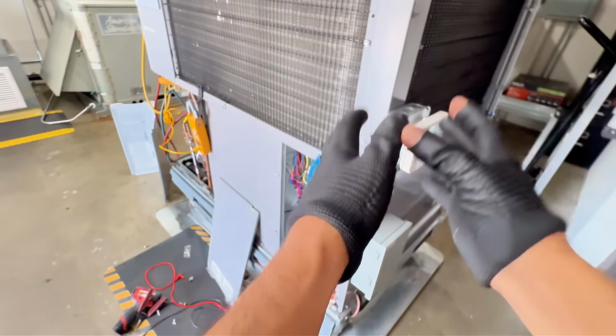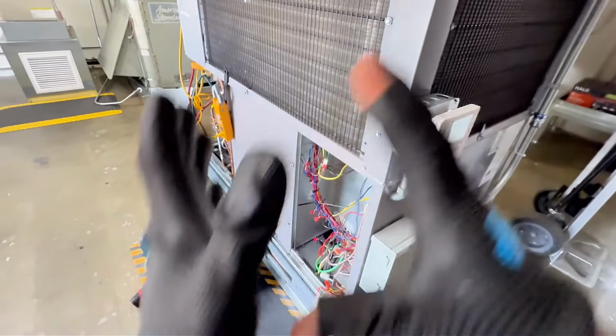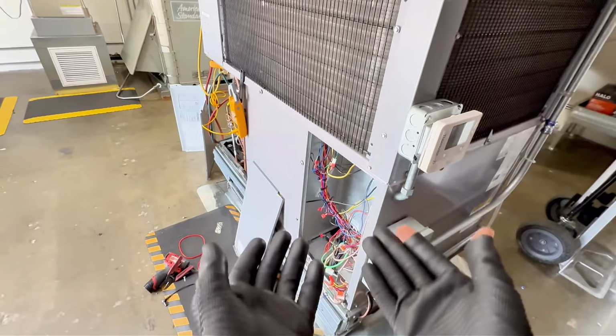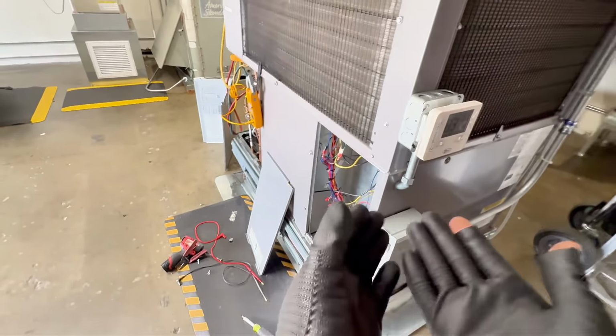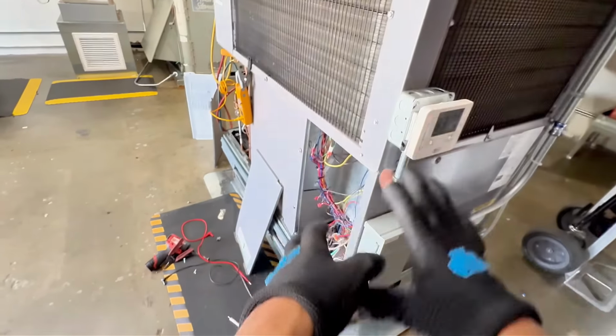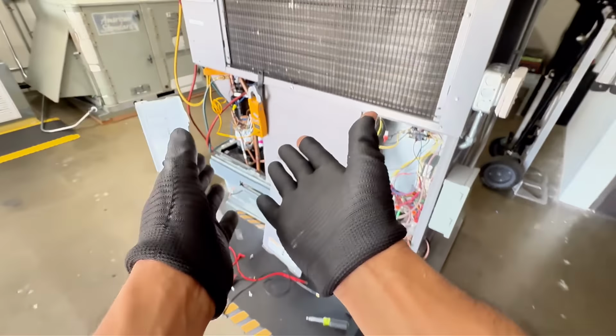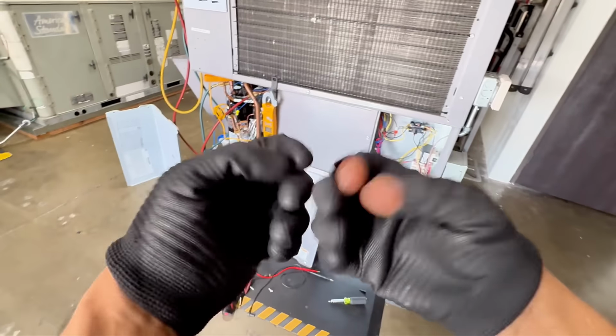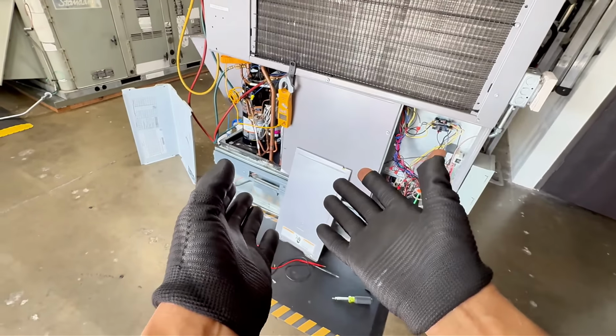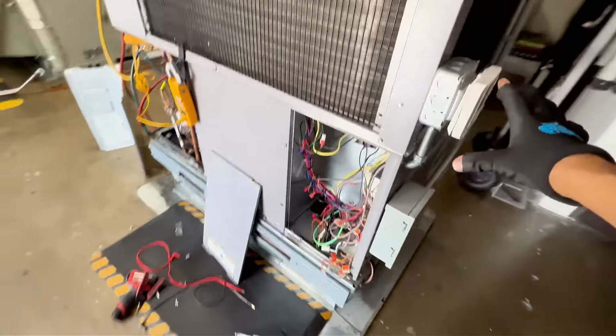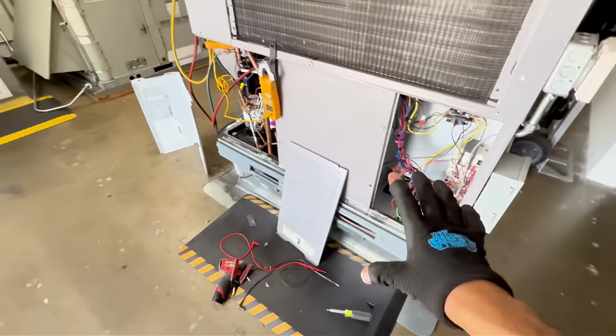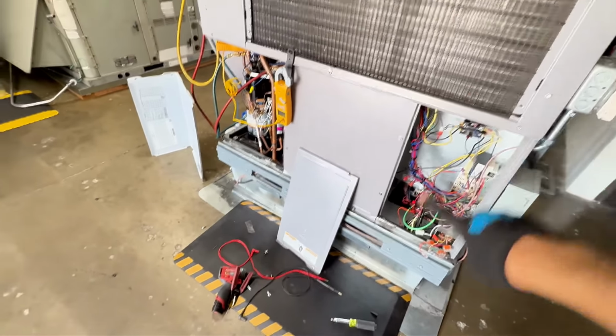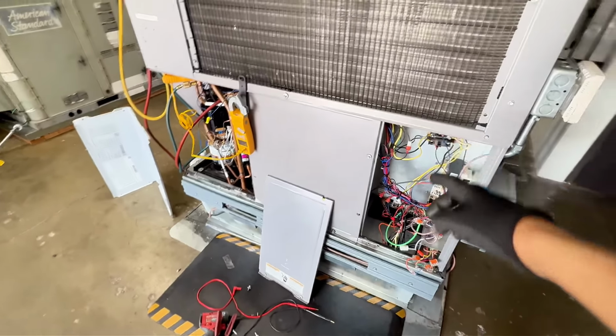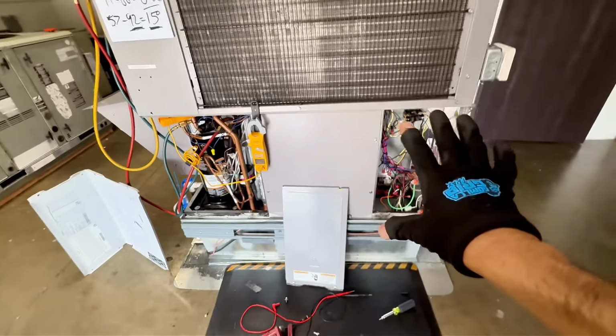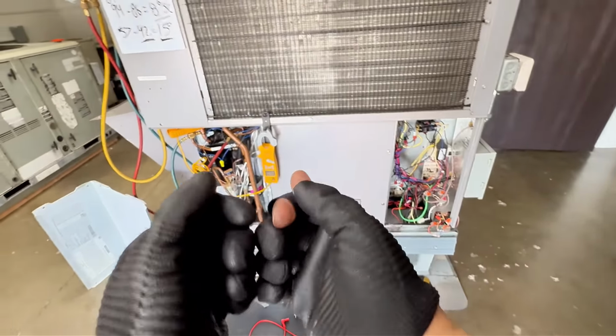Always start off with the easy things, with the control side, with the 24 volt side. Of course, if you smell something that's burned, or your fuse or your breaker tripped, your low voltage might be okay. It might be a compressor, a high voltage load that pulled too many amps, or something that's grounded. But always start off easy, right? Understand the path that 24 volts takes to make it back to the contactor coil. And then isolate. Okay, it's not a low voltage issue. It's not turning on. Let me check pressures.